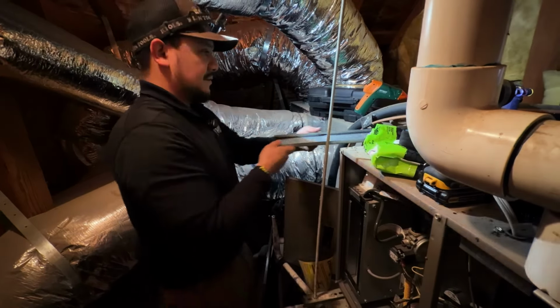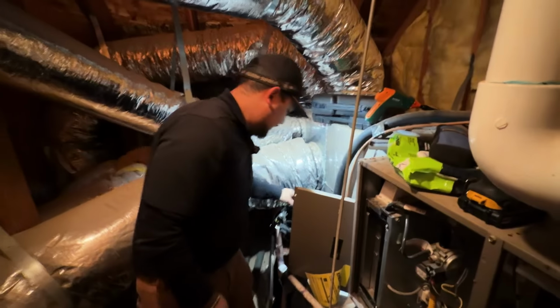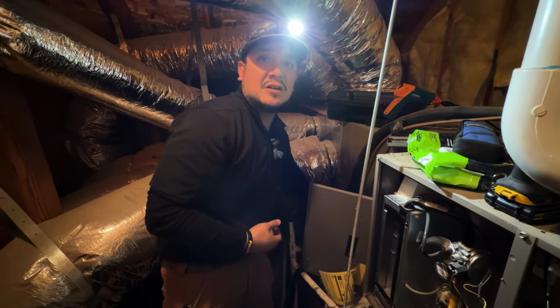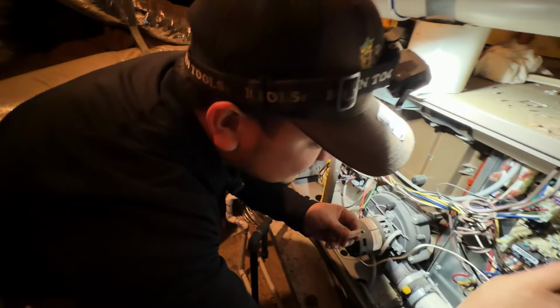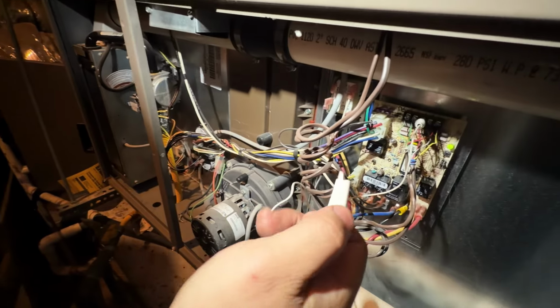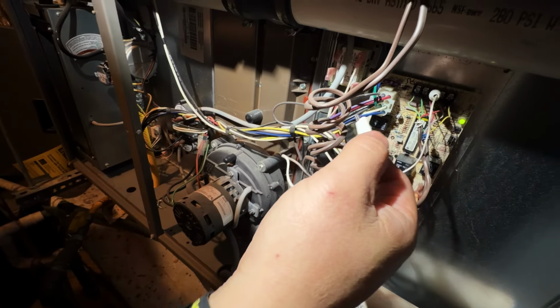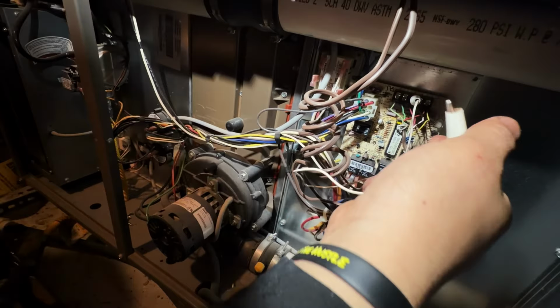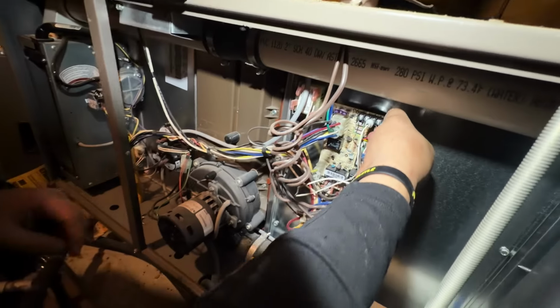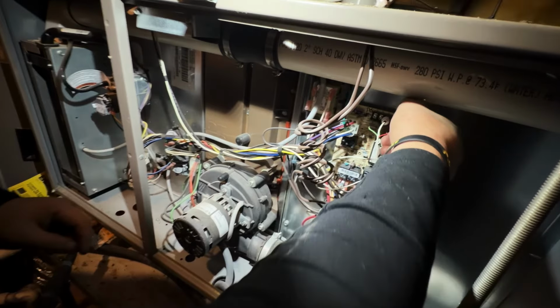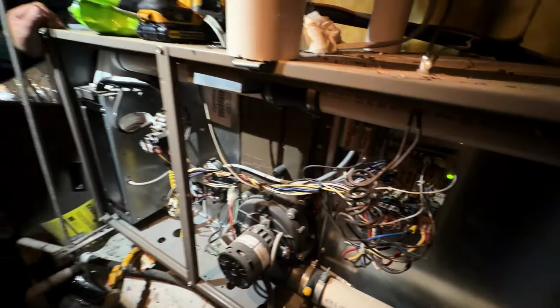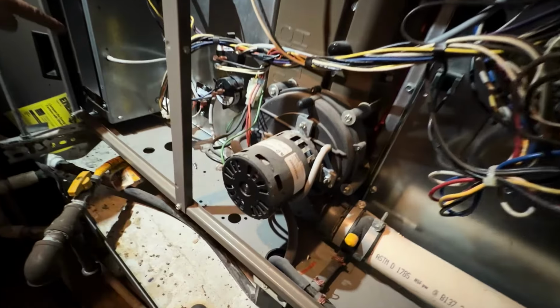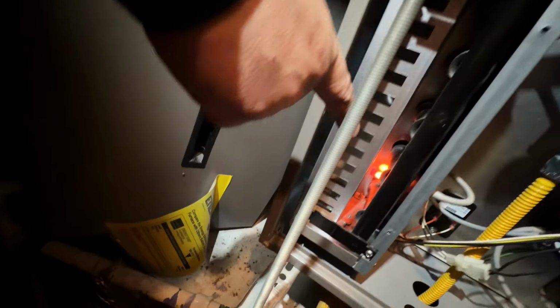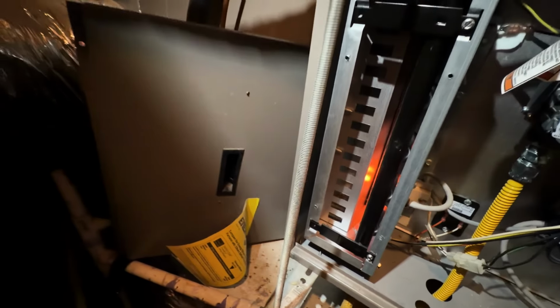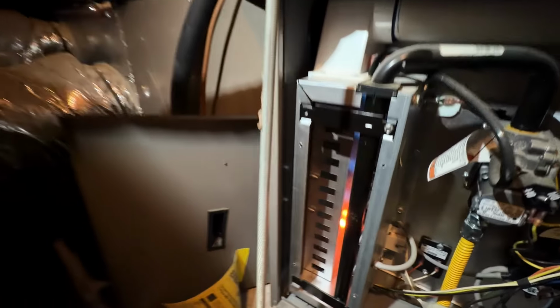Just be careful, this unit is still live, so watch out. Check those burners out. Now I'm going to jump into heating mode and check that vent to see if the smoke she mentioned comes out. I can manually jump it here to test it, putting it on the R terminal, which is 24 volts, and sending that to the W terminal, your heating terminal, bypassing the thermostat. The inducer motor turns on, the hot surface igniter is about to kick on, and then the gas valve is going to kick on right now. There you go.